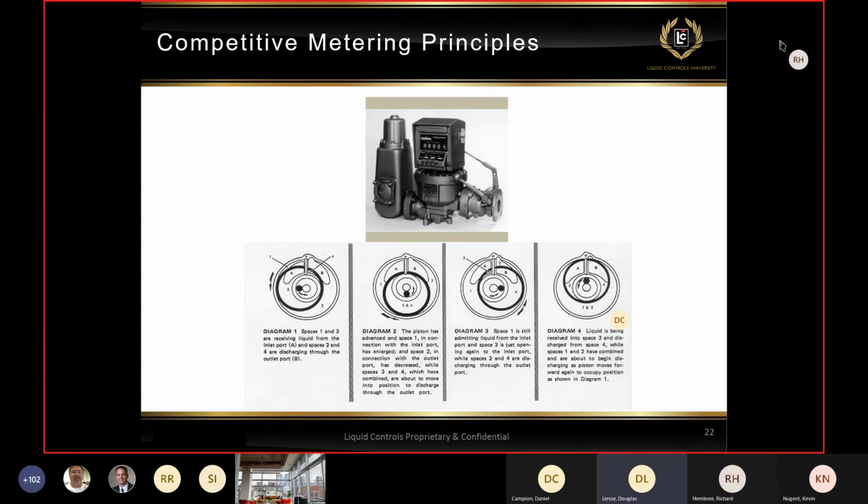They've now tried to do other materials to make it much lighter weight. But by sacrificing the original design, such as the piston being a hard-coated anodized aluminum, they are also causing it to wear more. So this is one where the accuracy changes over time. Therefore, having it calibrated at least on an annual basis is a necessity. Without that, they're going to be giving away product. And a seller certainly never wants to give away any product.